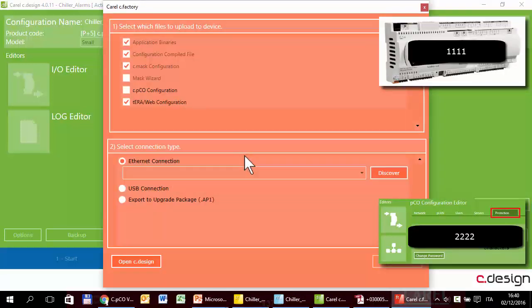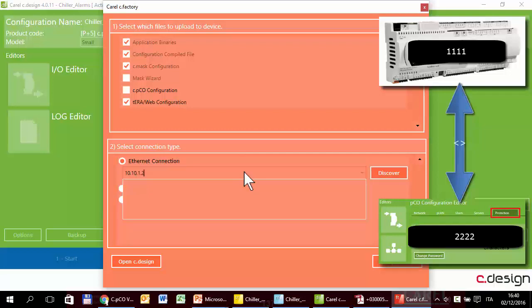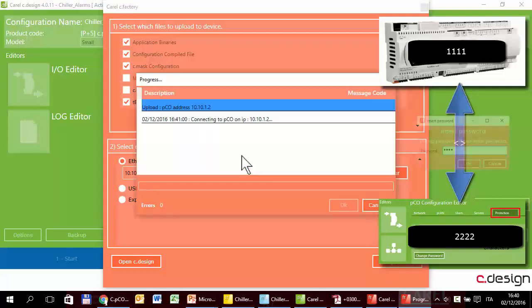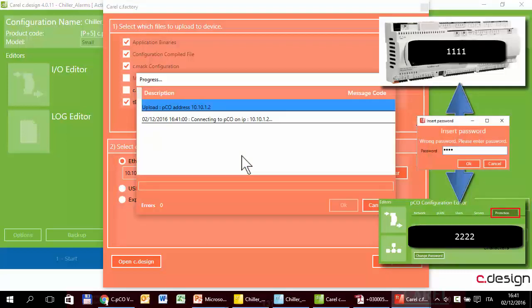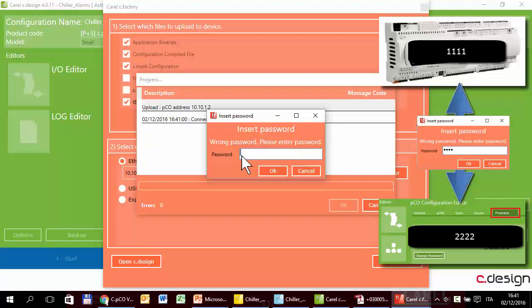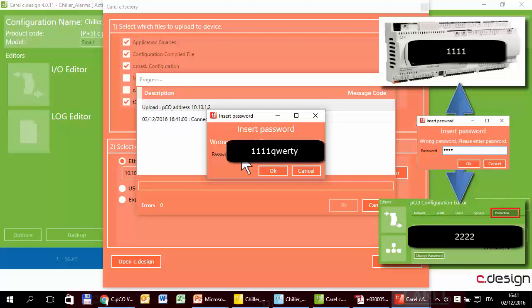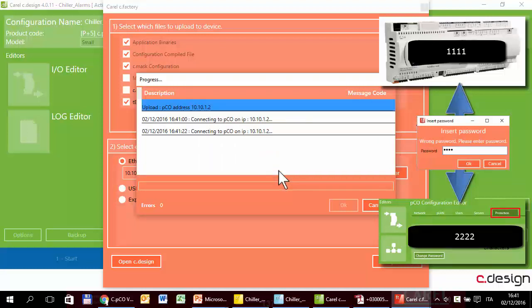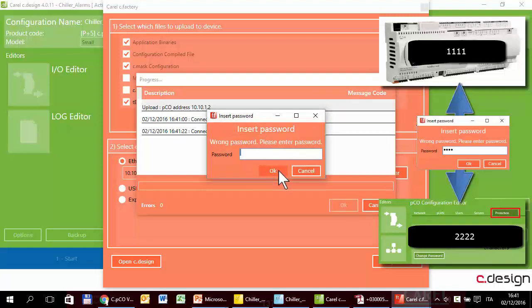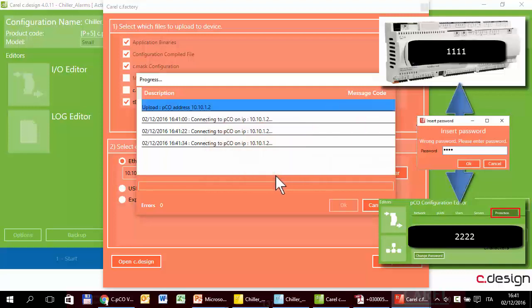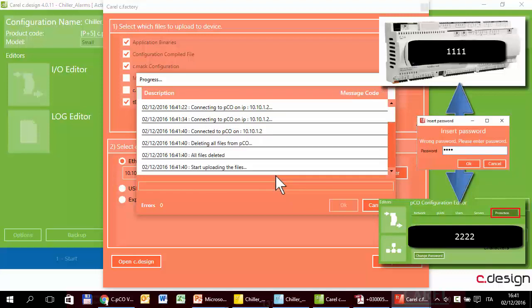Upload. Now the controller is protected with 1111 and the configuration has 2222 — the passwords are different. So when I try to upload, the system asks for the password of the controller. If I am the manufacturer or installer and I know the controller password, I can insert it. I try a wrong password first — it checks and it doesn't match, so it asks again. The right password of the controller is 1111, and the upload continues.